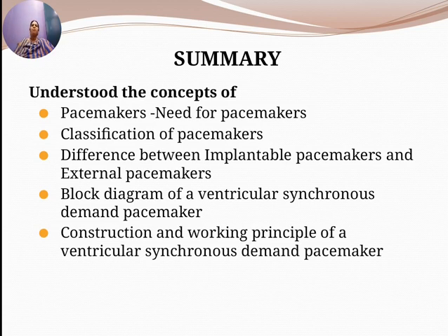They are competitive pacing mode, that is asynchronous mode, and non-competitive pacing mode, that is synchronous mode. Asynchronous pacing is called competitive pacing because the fixed rate impulses may occur along with the natural pacing impulses and would therefore be in competition with them in controlling the heartbeat. Non-competitive pacemakers are generally programmed either in demand or synchronized mode.